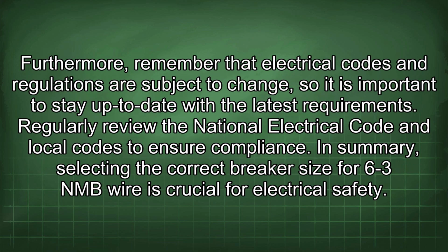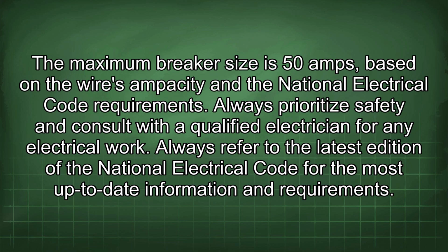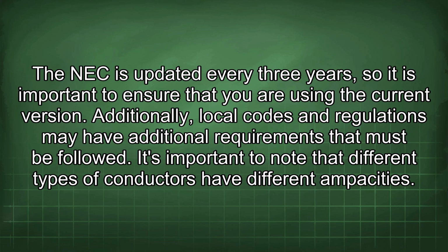Furthermore, remember that electrical codes and regulations are subject to change, so it is important to stay up to date with the latest requirements. Regularly review the National Electrical Code and local codes to ensure compliance. In summary, selecting the correct breaker size for 6-3 NMB wire is crucial for electrical safety. The maximum breaker size is 50 amps, based on the wire's ampacity and the National Electrical Code requirements. Always prioritize safety and consult with a qualified electrician for any electrical work. Always refer to the latest edition of the National Electrical Code for the most up-to-date information and requirements. The NEC is updated every 3 years, so it is important to ensure that you are using the current version. Additionally, local codes and regulations may have additional requirements that must be followed.